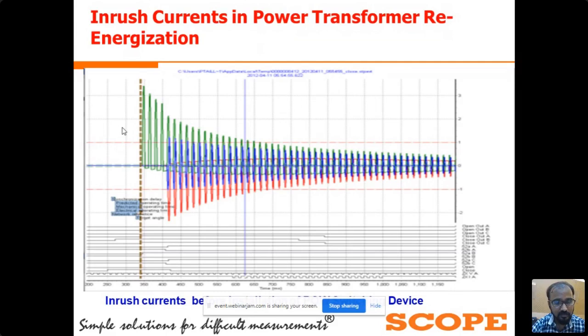At the time of opening we don't have control, and during this random operation we don't have any control on the closing of the CB contacts. Due to this random operation, you can see how much inrush current we have observed during the energization of the power transformer. Here we have combined the current graphs of all three phases. The graph in red is the R phase waveform, the green is the Y phase current waveform, and the blue is the B phase current waveform.